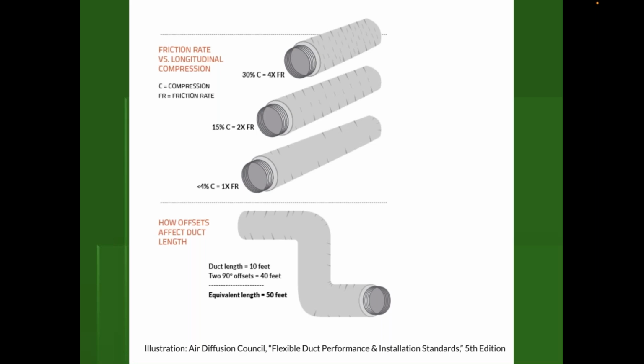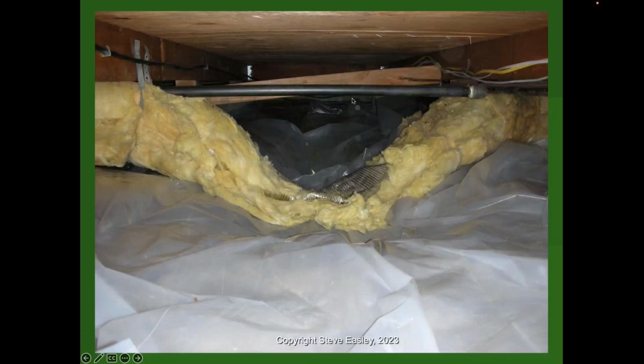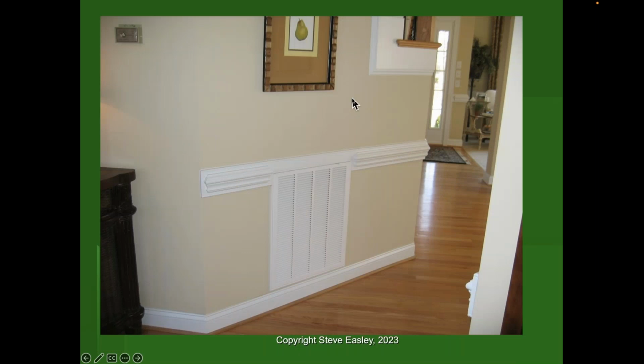And this is really important for heat pumps because airflow is what it's all about. The greater the airflow, the greater the comfort. And so making sure that we stretch the ductwork, we use elbows at these conditions, metal elbows instead of just bending the flex duct. Also, inspection is really, really important. And then these types of grills are just the kiss of death in terms of proper airflow.